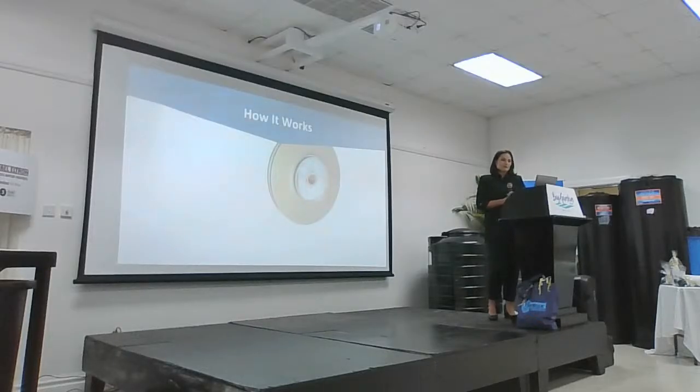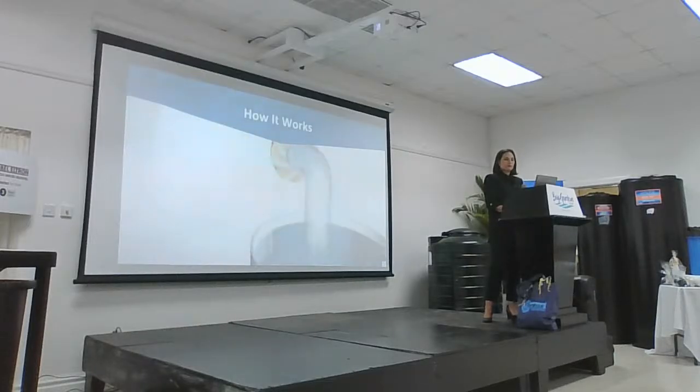This imparts centrifugal force to water particles, and the water moves radially out. Since rotational mechanical energy is transferred to the fluid, at the discharge side of the impeller, both pressure and kinetic energy of water will rise. At the suction side, water is getting displaced, so a negative pressure will be induced at the eye. Such low pressure helps in sucking a fresh water stream into the system again, and this process continues.